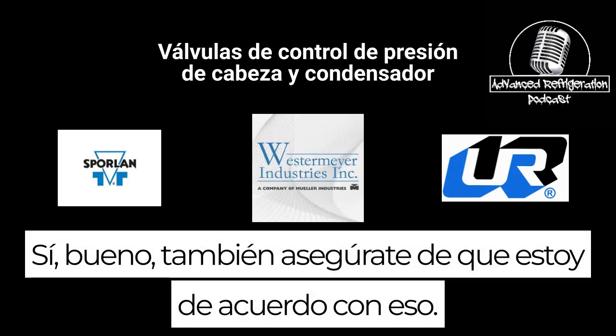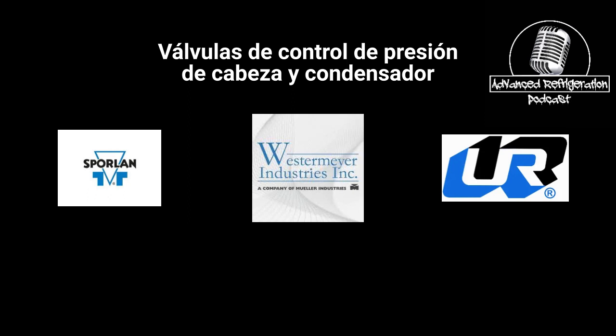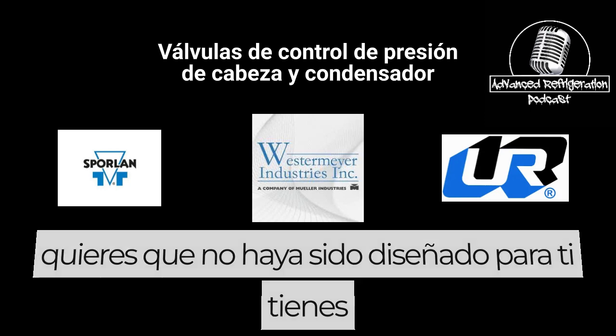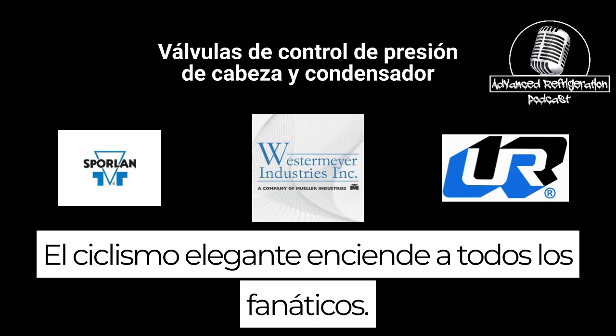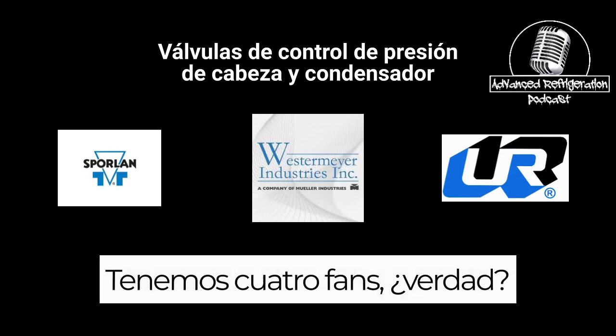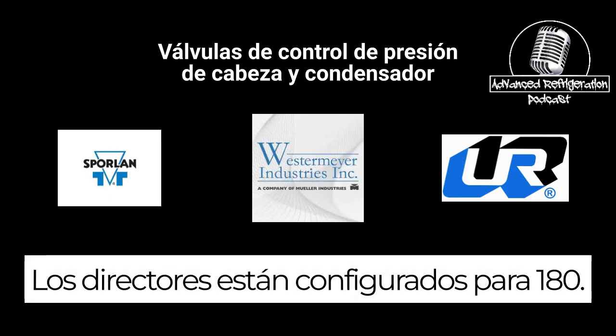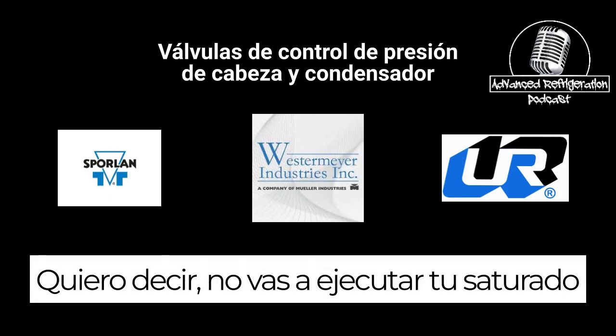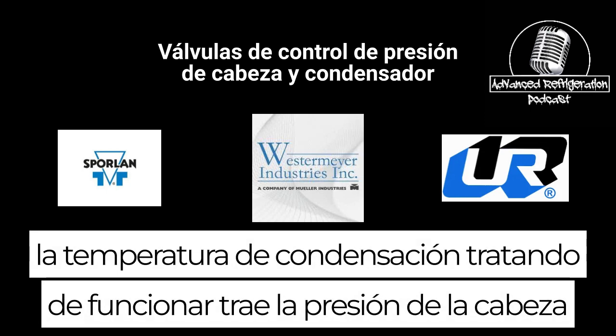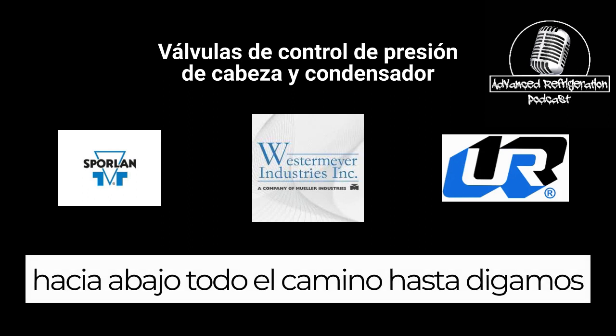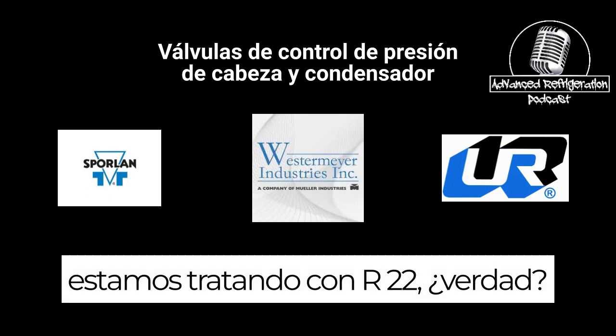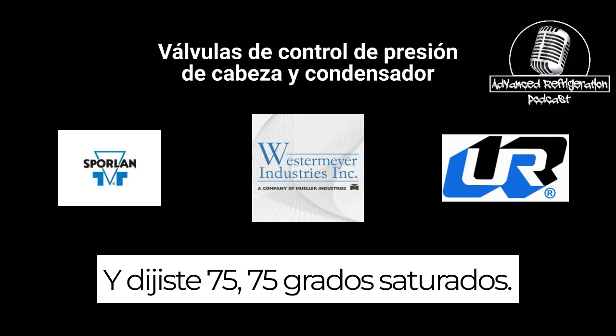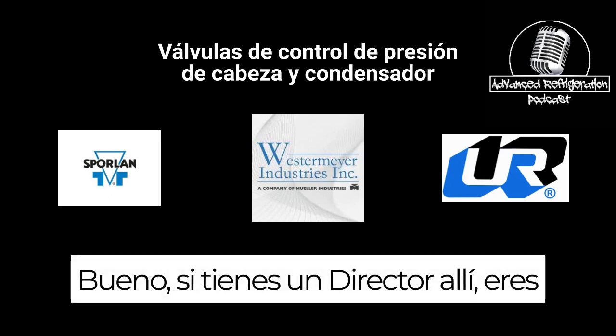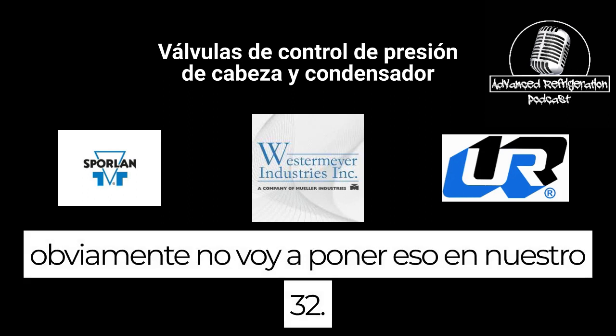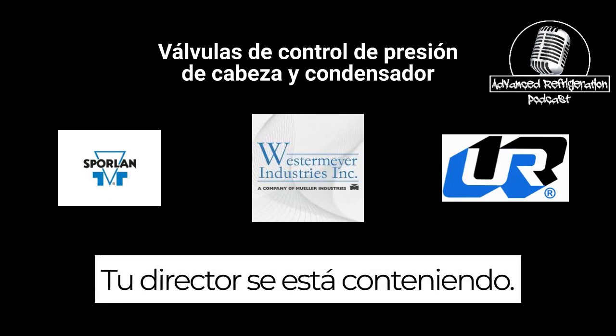Yeah, I agree with that, but the system has a headmaster. I've always been taught that you don't want the head pressure lower than it was designed for. If you have fan cycling switches on every single fan motor, let's say we're dealing with a unit with 4 fans, and the headmaster happens to be set for 180, you're not going to run your saturated condensing temperature trying to bring your head pressure all the way down. Let's say we're dealing with R22, and you said 75 degrees saturated, that brings you down to 132. Well, if you have a headmaster on there, you're obviously not going to set it for 132 if your headmaster is holding back at all.